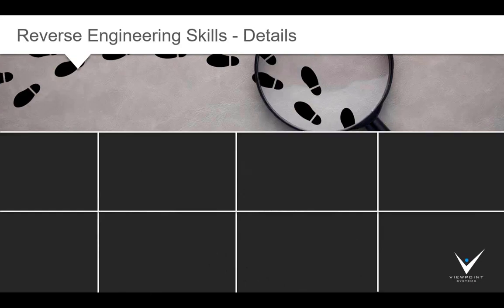Okay, so some pieces to consider during an upgrade. The first is understand your signal path. You want to understand everything that happens to the signals being measured, starting at the sensor and ending with the A to D values. Consider items such as sensor models, signal level and bandwidth, connection interfaces to the UUT, the unit under test, wire types, whether they're shielded or twisted pair, signal conditioning, and so on.